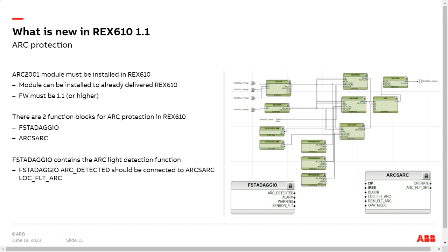Of course, the one thing is that you need to have firmware version 1.1 or higher, so you need to update the device. I will mention that later in the presentation. As mentioned already, there are two function blocks for the arc protection: this arc function block as well as this arc protection block, which can be seen in the pictures.